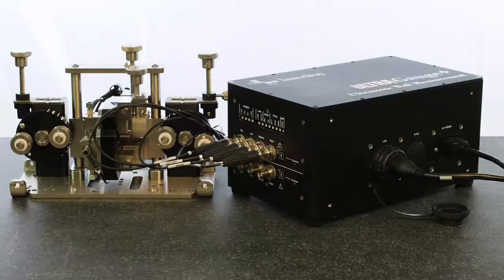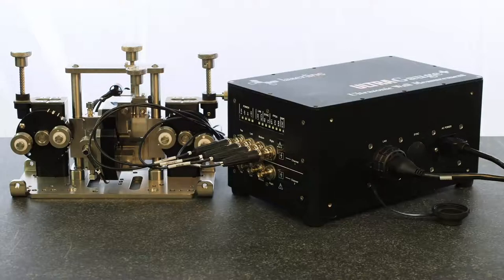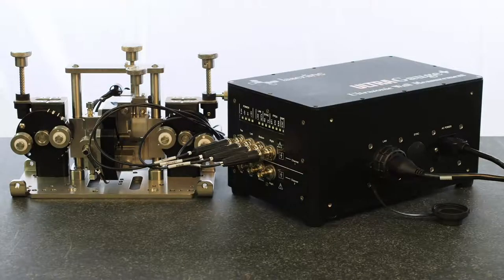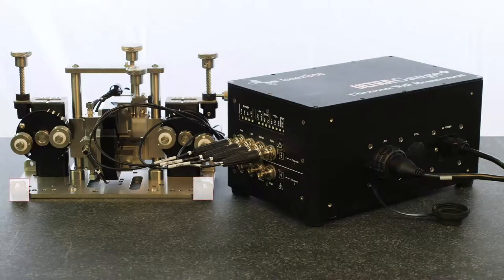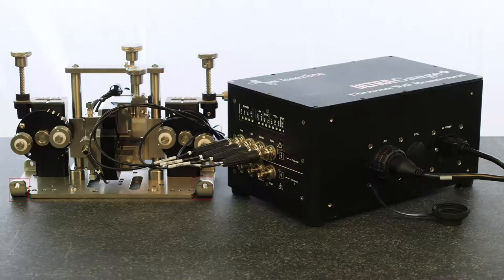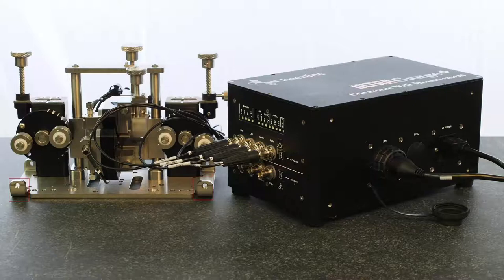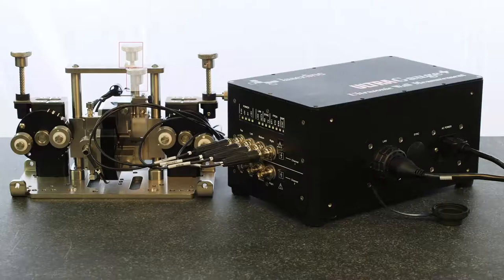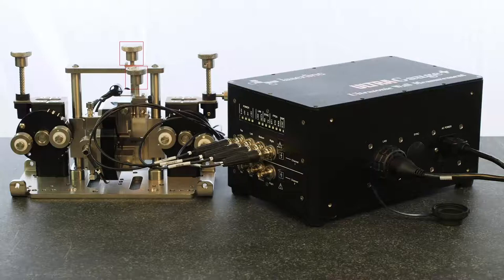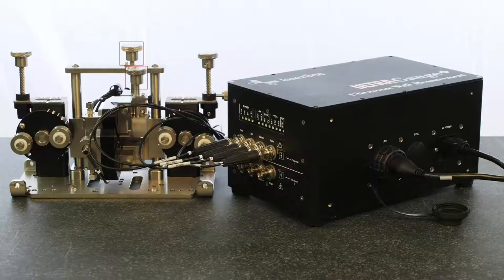Now the sensor assembly can be mounted into the tank. There are mounting screws on the sensor assembly to assist with positioning. Thread quarter 20 screws into the sheet metal tabs to press up against the tank wall to prevent the sensor assembly from moving or rotating. There are also two knobs on the top of the sensor assembly. These knobs are labeled up, down, and left, right, and allow for the user to move the transducer ring up and down or left and right in relation to the product in order to center the ring around the product.